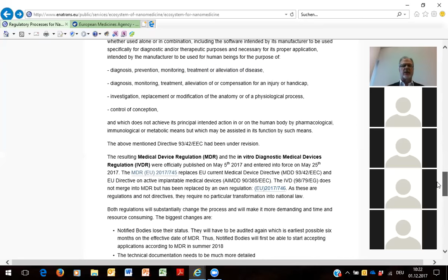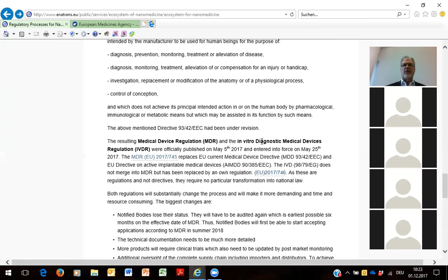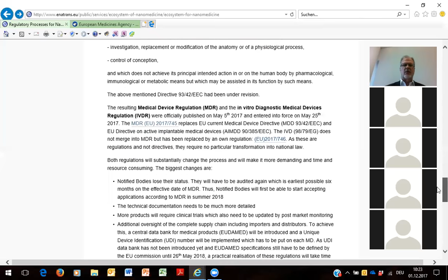Now, as I told you, the medical directive is now being replaced by a medical device regulation. The difference between a directive and a regulation is that the regulation, which has been published this year in May 2017, applies to whole Europe and doesn't have to be adapted to the national law. It becomes basically national law. This is very different to the directive, where member states had a lot of freedom to set specific rules and regulations within this directive. Now, this regulation comes into force within 3 or 5 years, depending on whether you talk about the devices or the in vitro diagnostic regulation. And these regulations have a huge impact on the medical devices.